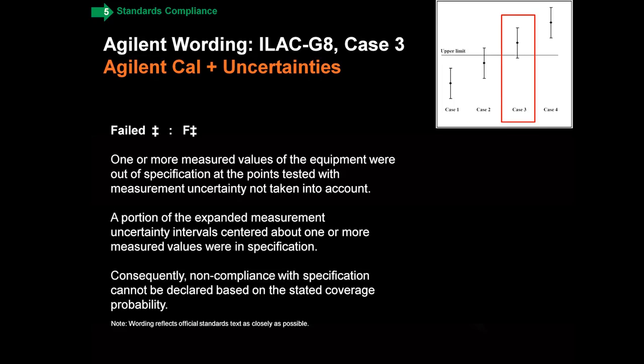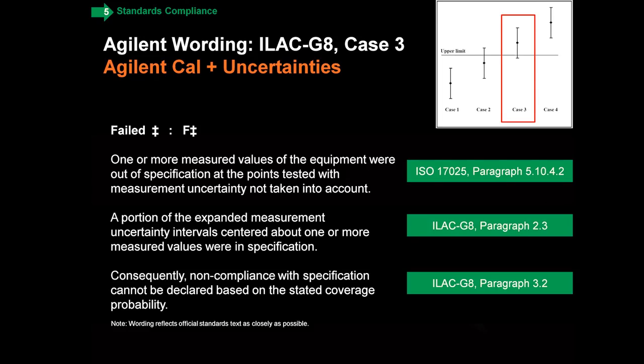Similarly, in the case where you observe it to fail — in other words, it's outside the spec as observed — but a portion of the measurement uncertainty also crosses, we have similar wording. You'll notice that we line those up with the key paragraphs in either 17025 and ILAC G8. So when 17025 says measurement uncertainty shall be taken into account, you'll know exactly how we've done that — we've lined it up and made it very precise for you.